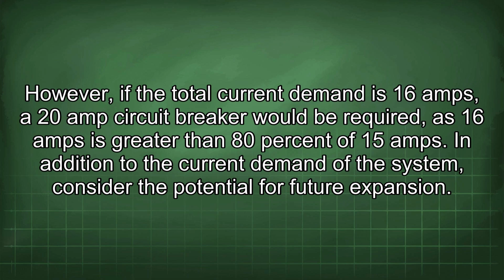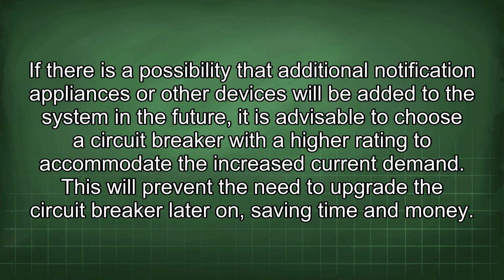In addition to the current demand of the system, consider the potential for future expansion. If there is a possibility that additional notification appliances or other devices will be added to the system in the future, it is advisable to choose a circuit breaker with a higher rating to accommodate the increased current demand. This will prevent the need to upgrade the circuit breaker later on, saving time and money.